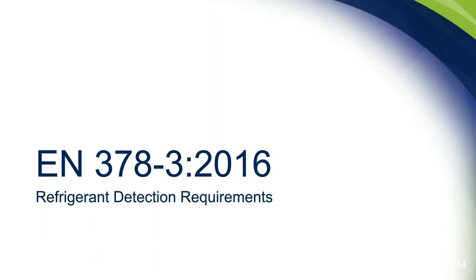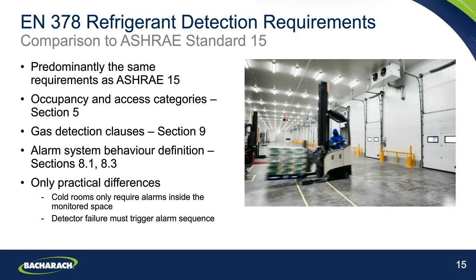So if we then compare that to the primary European regulation regarding refrigerant safety standards and leak detection, EN 378-3, the 2016 version, we can see here that the requirements are predominantly the same as we see in ASHRAE 15. Occupancies are defined differently, but ultimately give us broadly the same results, and you can find those in section 5 of this standard. And the gas detection clauses within there are in section 9, and they link into sections 8.1 and 8.3, which define the alarm system behavior.